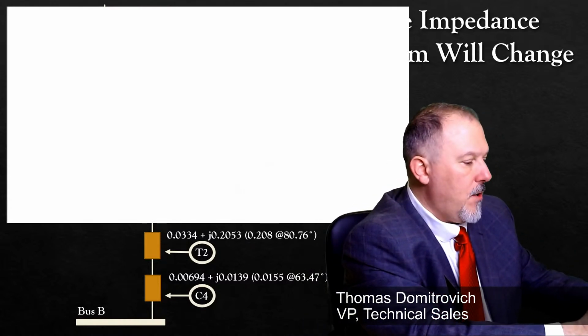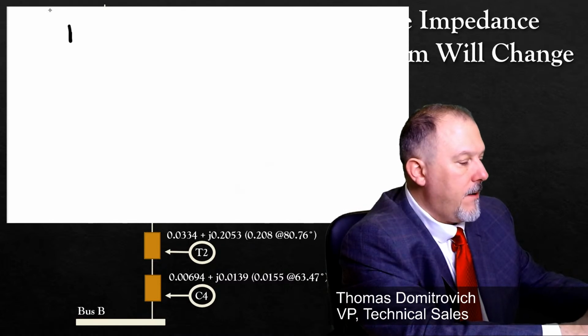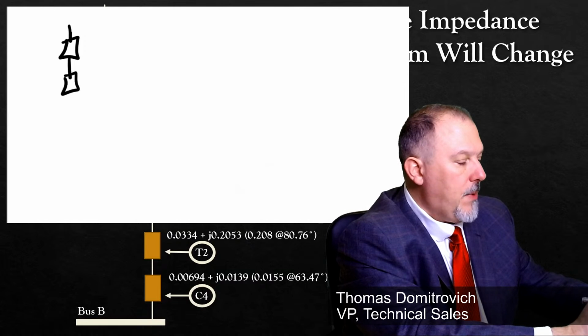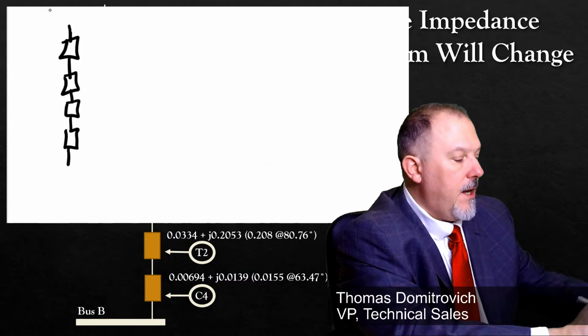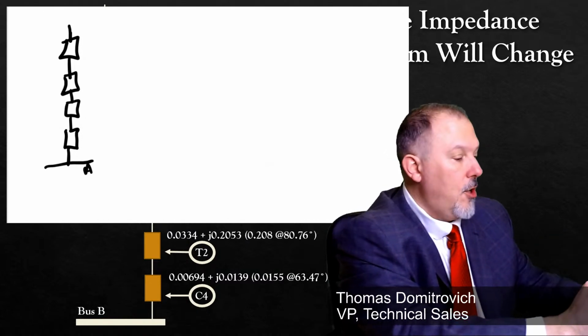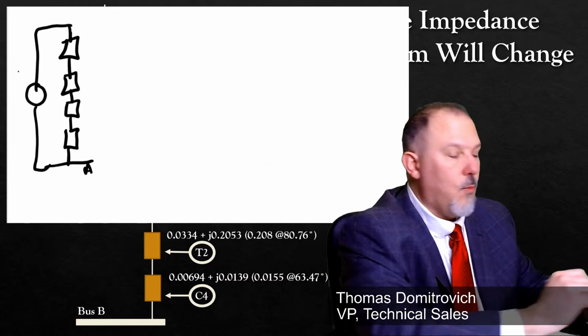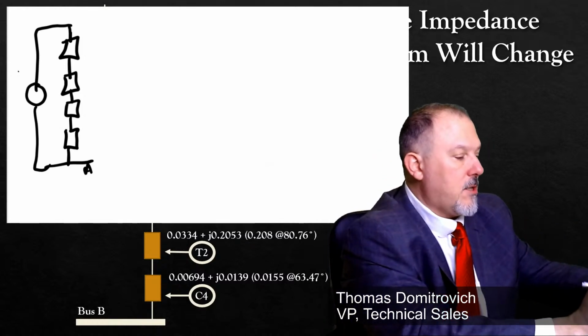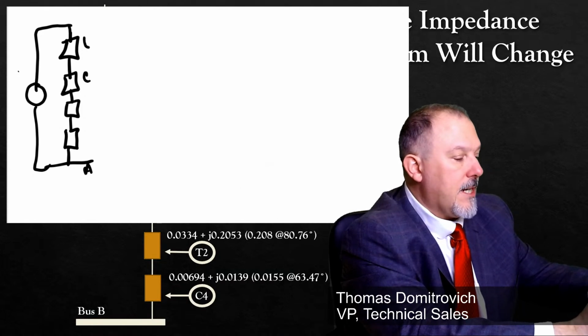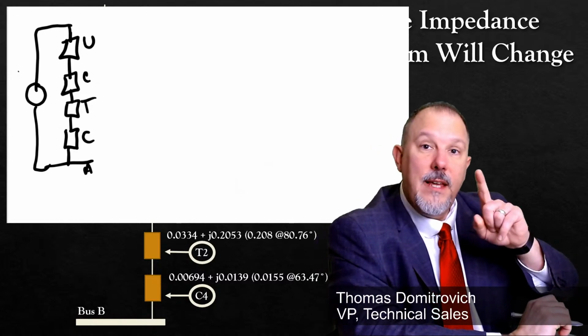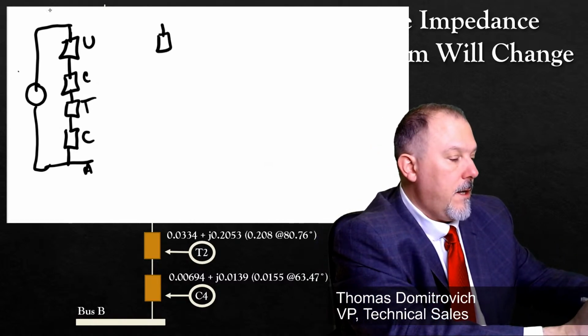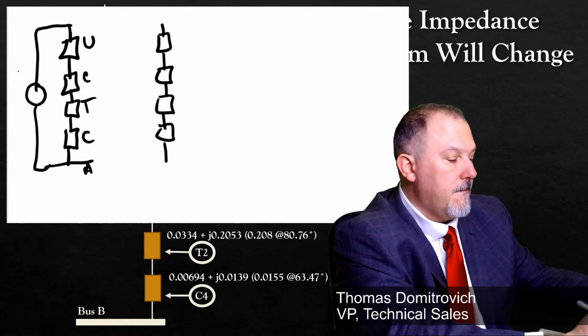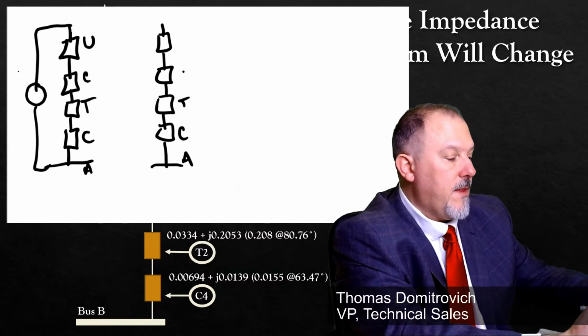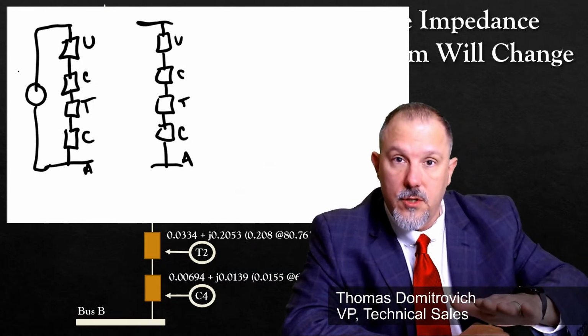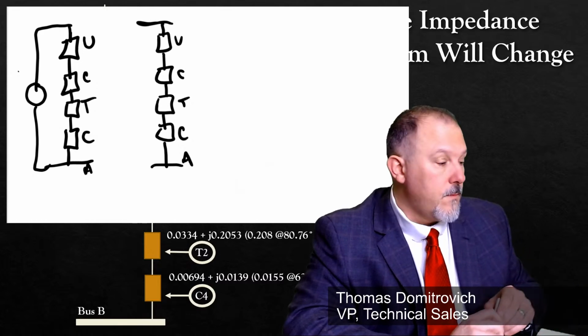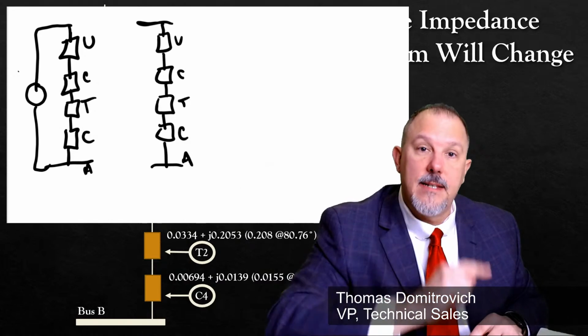Now, when you think about what we have in the positive sequence, we had the impedance of the utility, the impedance of a conductor, the impedance of a transformer, the impedance of a conductor, and then you had bus A, right? And we always come back with a voltage source, and this is 1 at the angle of 0 per unit. And those are our impedances. So this is the utility, conductor, transformer, conductor. The negative sequence is the same thing. Bus A. That's the conductor, that's the transformer, that's the conductor, that's the utility. There's no voltage source in the negative sequence circuit. The impedances are exactly the same.